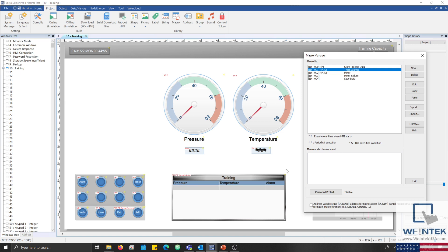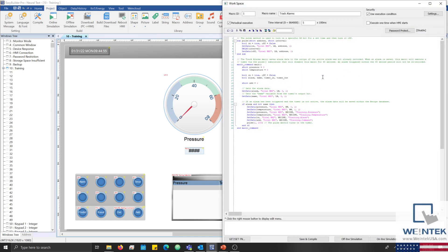After an alarm occurs, our macro enables a timer that runs for 90 seconds. While the timer is active, any additional occurrences of the alarm will be considered as though they are related to the original occurrence, and process data will not be stored within our database.